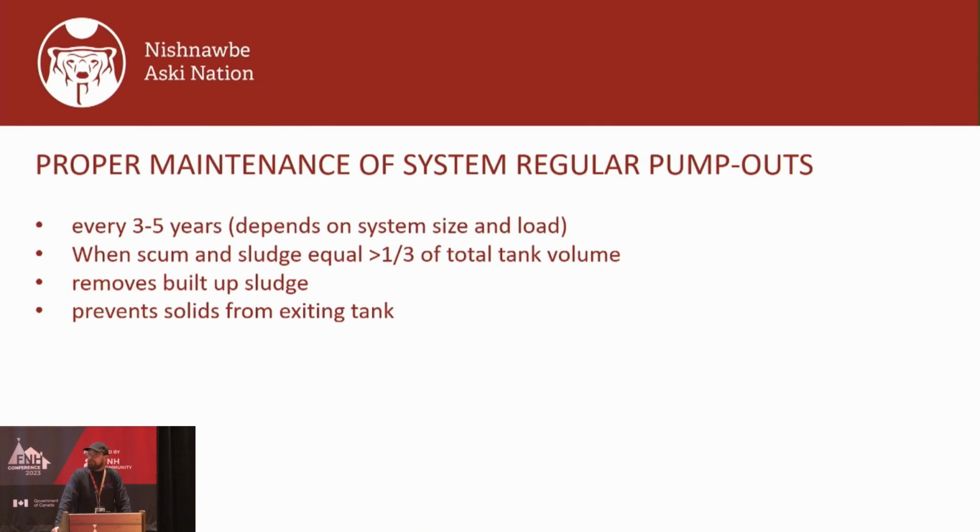I know like a lot of truck haul systems, it's as required. Those aren't septic systems per se. Those are what I would call a holding tank. You also are supposed to pump it when the scum and sludge is greater than 1/3 of the total tank volume. And what that does is it prevents solid from exiting the tank and just adds more treatment capacity.